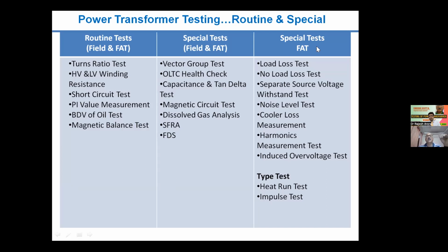But these tests are also performed, especially on the transformers in the field as well as at the time of factory. Then some special tests. These tests may be taken as type tests or at the time of factory acceptance test. So load loss tests, no load loss tests, separate source voltage withstand test, noise level test, cooler loss measurement, harmonics measurement test, induced over voltage test, heat run test, and impulse test.